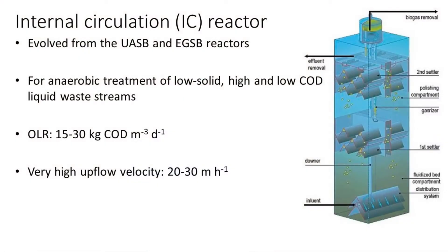A reactor that can solve that effluent restriction of solids washing out, but comes with more complexity, is the internal circulation reactor. This is a hybrid reactor — it has existed about 15 to 20 years. There are two stages, meaning at two different places in the reactor you collect biogas. They can be loaded quite highly, the same level as EGSB, and are good for streams with low solids, both high and low COD, and very good for calcium-rich streams. The upflow velocity is very high: 20 to 30 meters per hour.